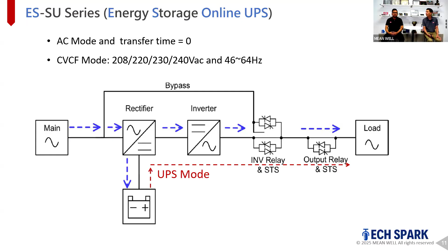The next one is eco mode. It's basically the combination between AC mode and bypass mode. The blue line on top is always in bypass, and anything that happens outside of bypass range goes into inverting mode. If there's a power outage, it goes to battery mode.